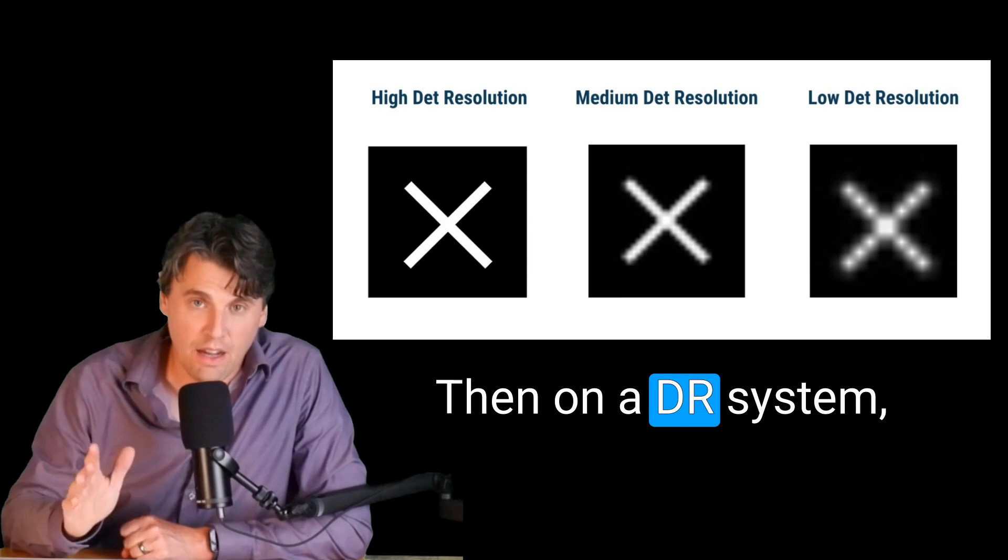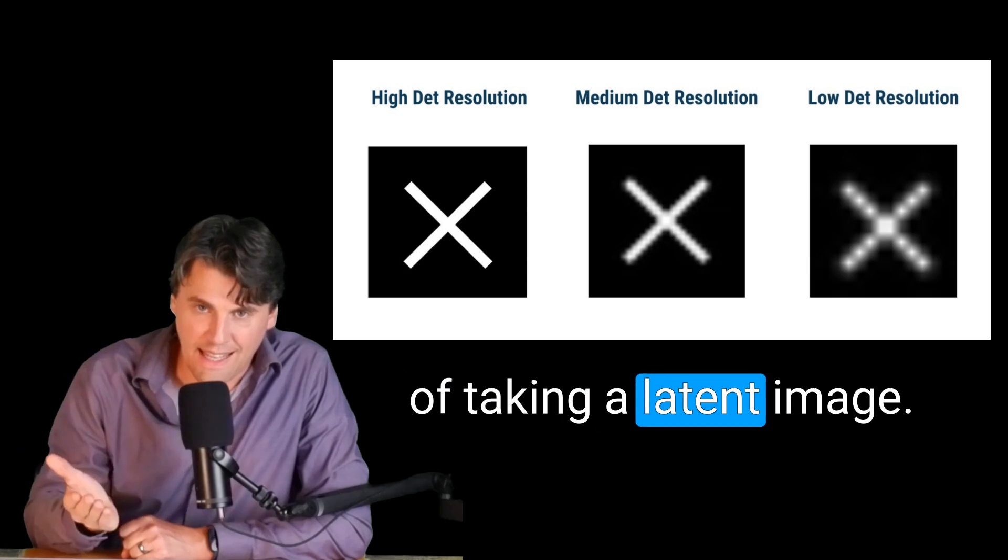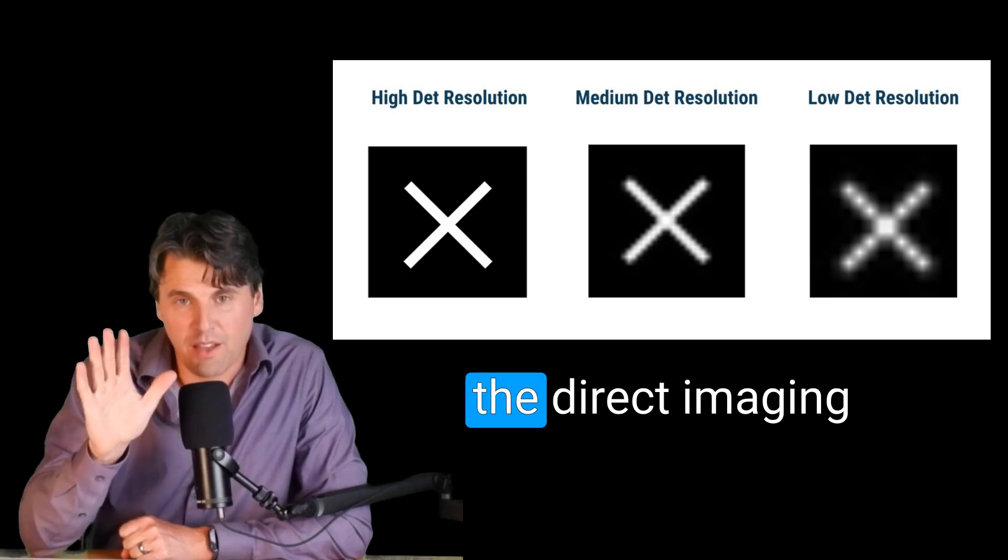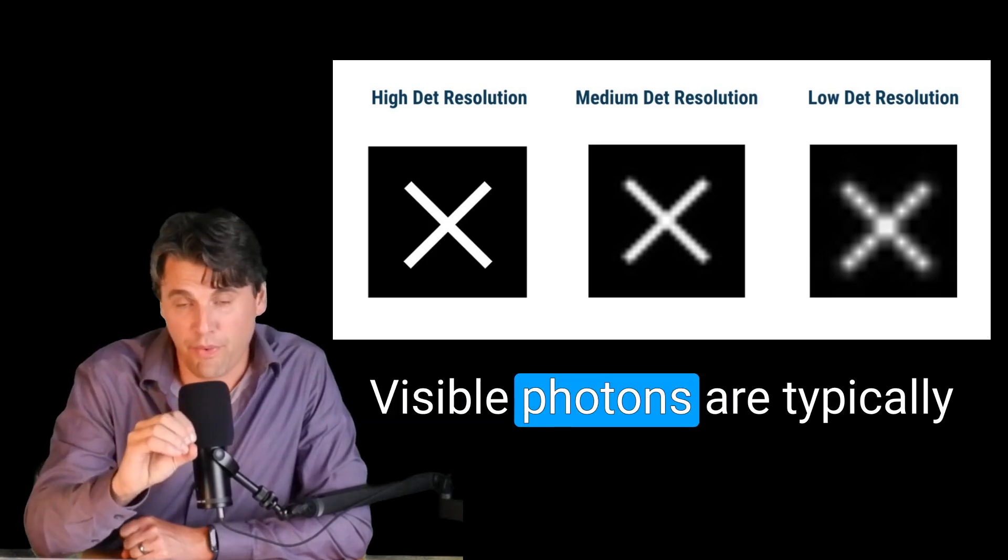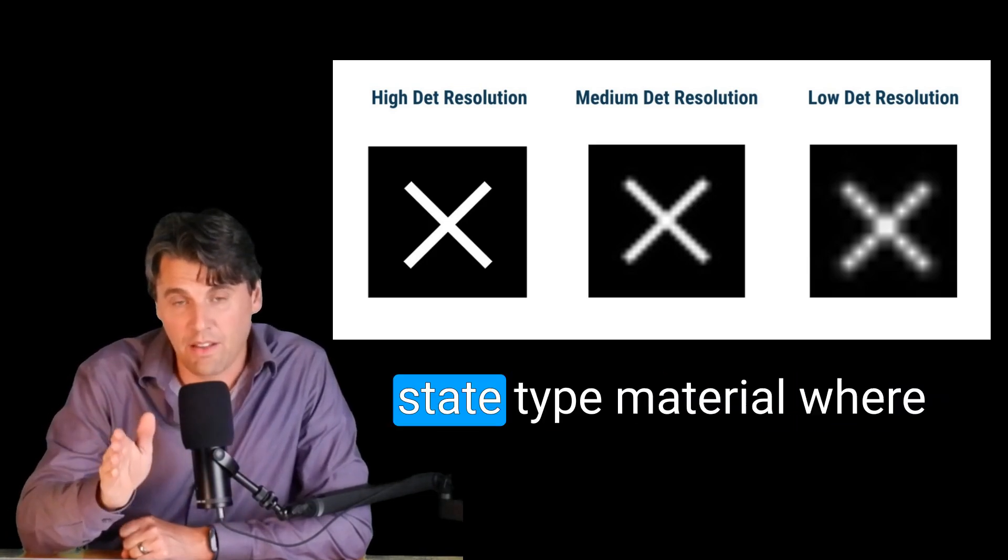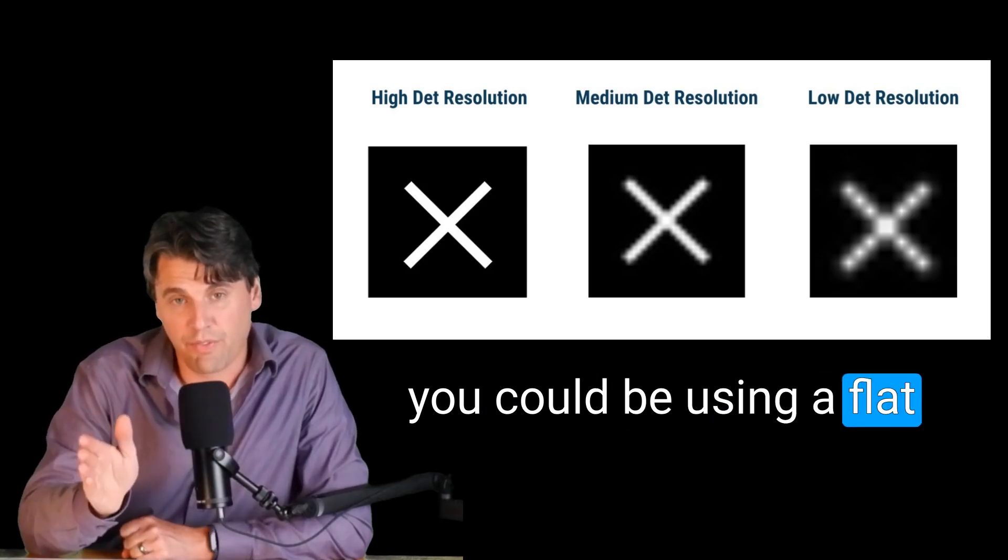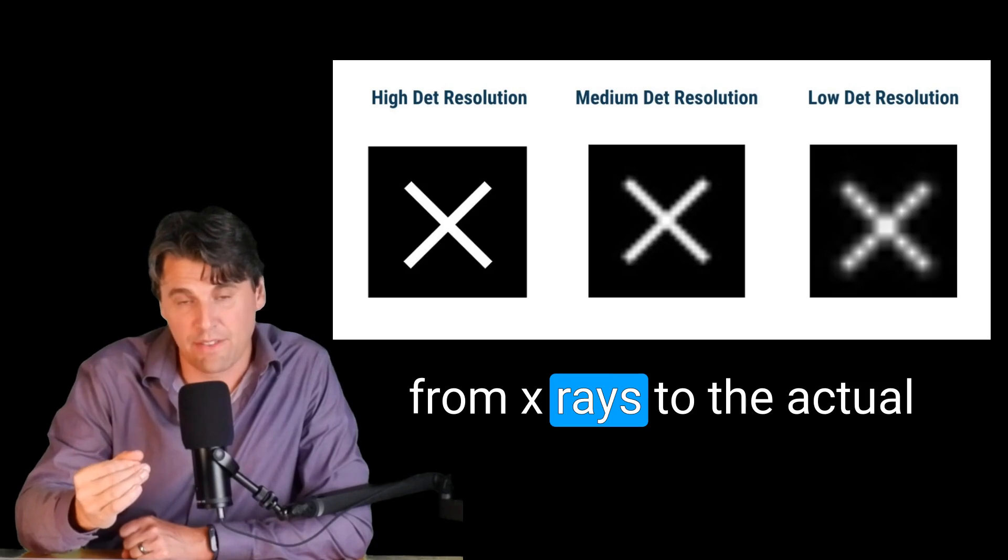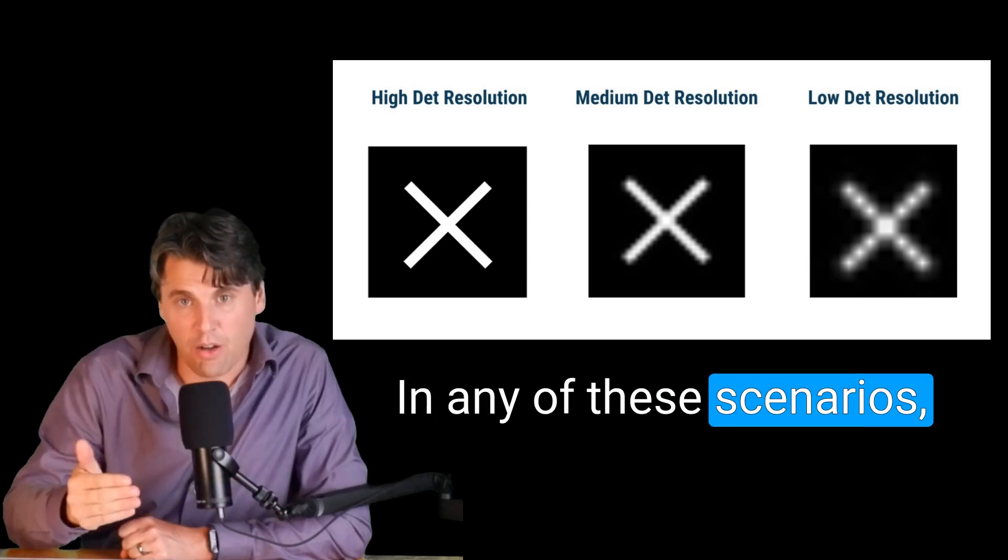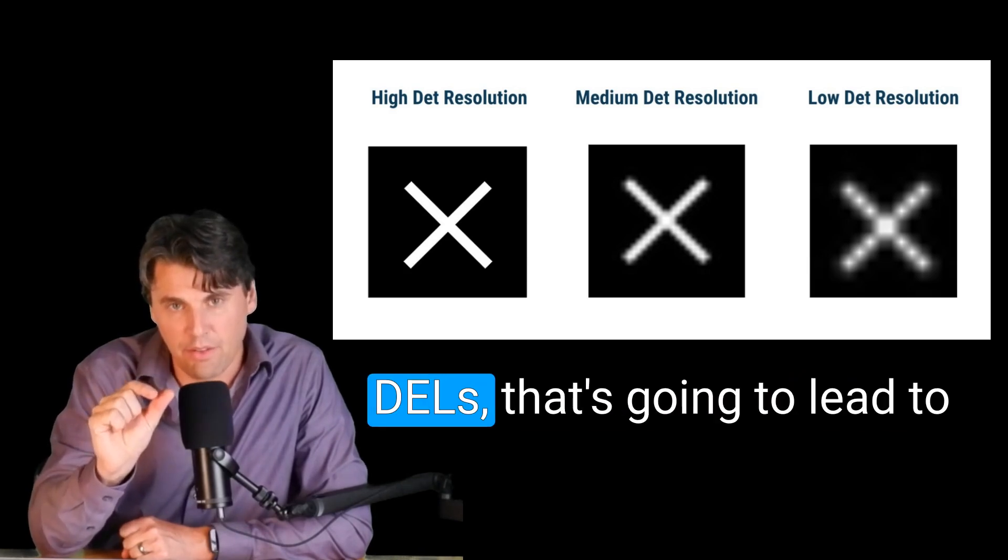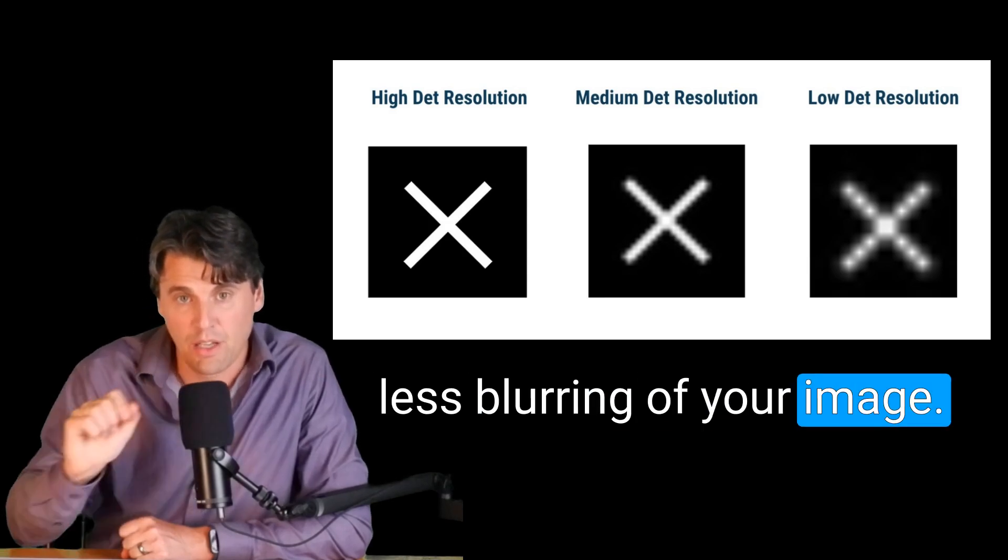Then on a DR system, we aren't doing that step of taking a latent image and generating visible light, we're actually using the direct imaging system. There's actually going to be a scintillator, visible photons are typically going to be generated, unless you're talking about a solid state type material, where you could be using a flat panel, and going directly from x-rays to the actual electrons themselves. In any of these scenarios, actually, the smaller the detector elements or the DELs, that's going to lead to less blurring of your image.